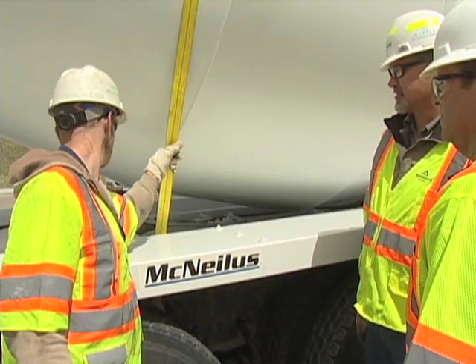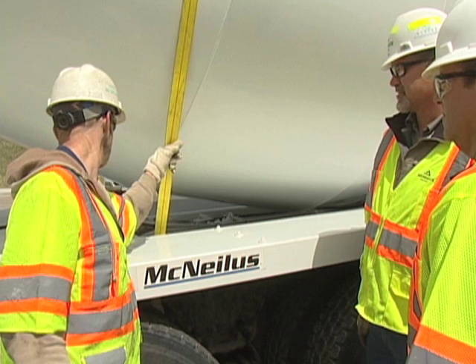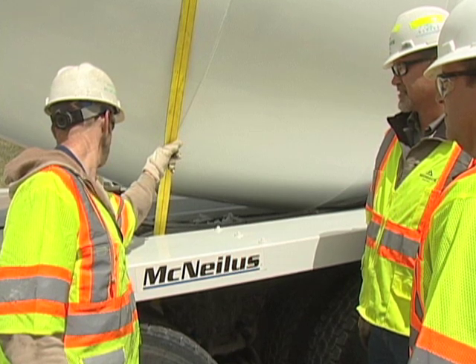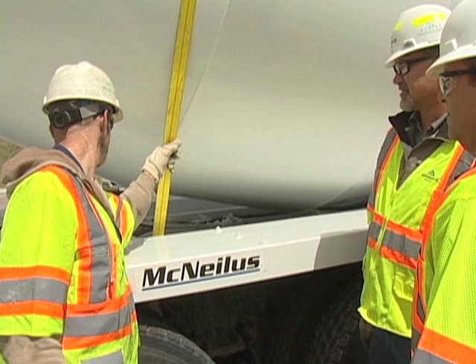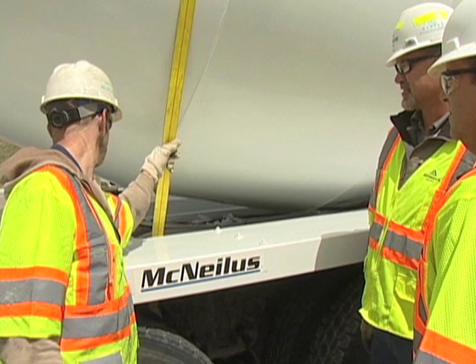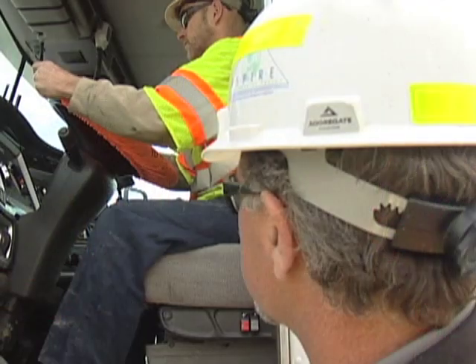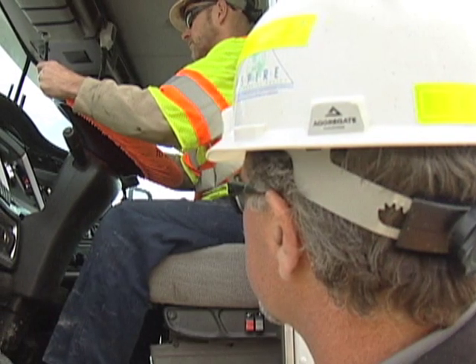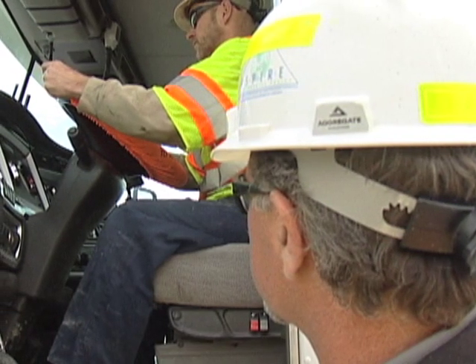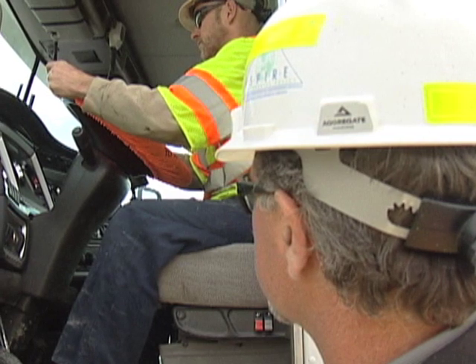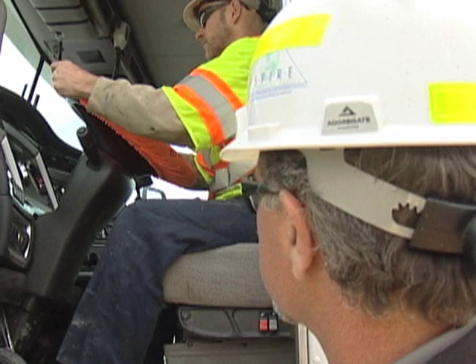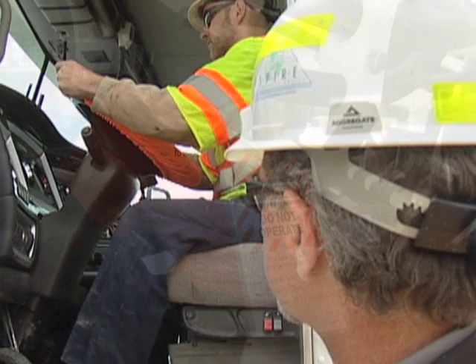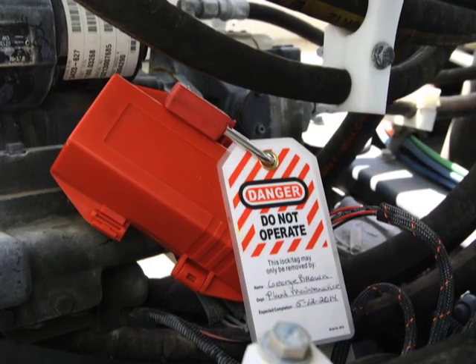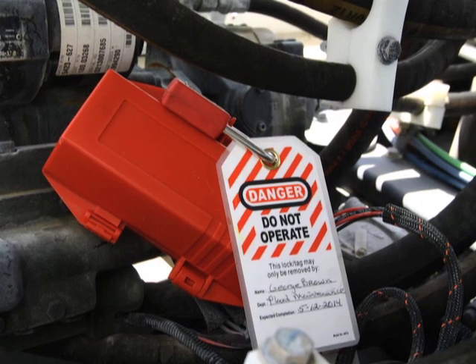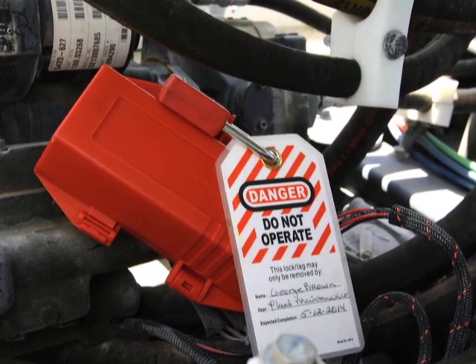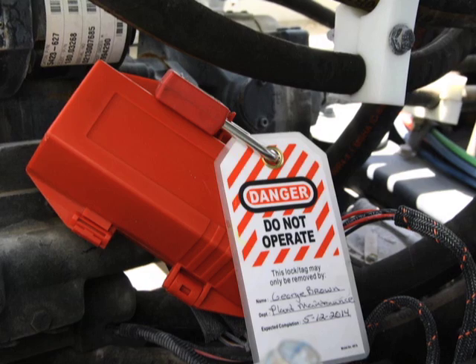Authorized employees are employees who have been extensively trained and have demonstrated their ability to apply and remove lockout, tagout, tryout devices on machines or equipment. They've also been trained and can demonstrate their skills in performing service or maintenance on affected equipment. These employees must be able to demonstrate proper lockout, tagout, and tryout procedures and have the knowledge to properly work on, install, inspect, and/or repair plant-energized equipment.